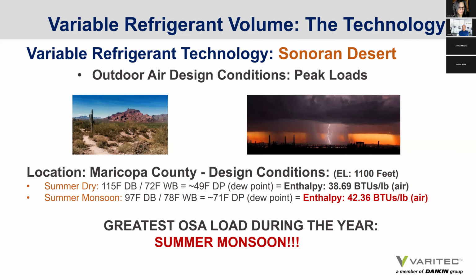the Sonoran Desert? We often associate our peak summer design condition in June, 115 degrees. Well, when it's 115 degrees, it's actually dry. Our peak summer design day is where the total enthalpy energy in the environment is actually greater, when it's 97 degrees dry bulb, 78 degrees wet bulb, or a 71 degree dew point, versus the 115 degree design day at a 49 degree dew point. So our peak summer design condition is monsoon, which we see anywhere from the beginning of July right the way through mid-September. We've seen it.